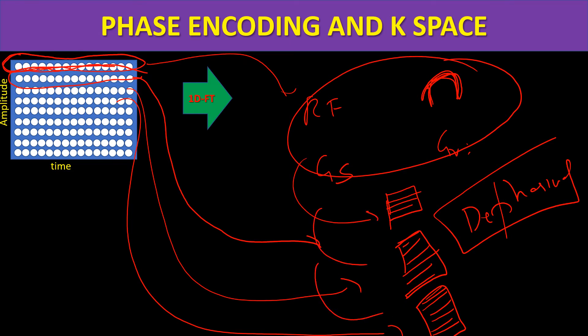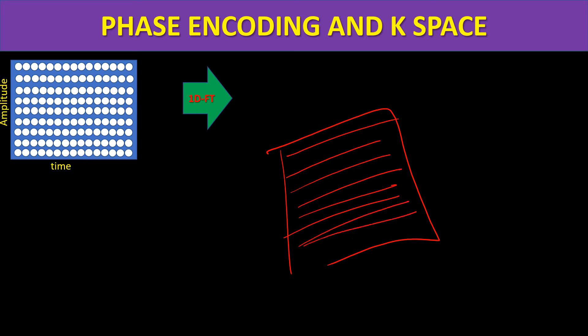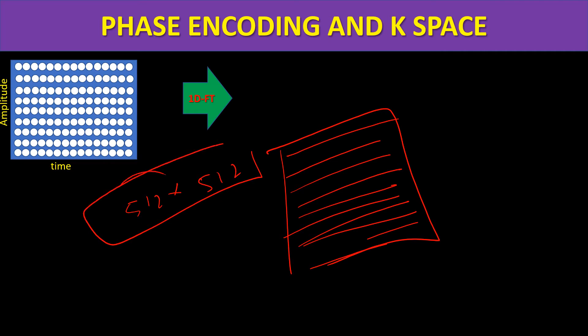By giving multiple dephasing gradients, I repeat the same process for each step. I take the same slice and measure it multiple times. The number of times I have to measure depends on the number of phase encoding steps I want. For a 512×512 matrix, I have to repeat the entire step 512 times to fill 512 lines in k-space. This is how we fill k-space — each line represents one phase encoding step.